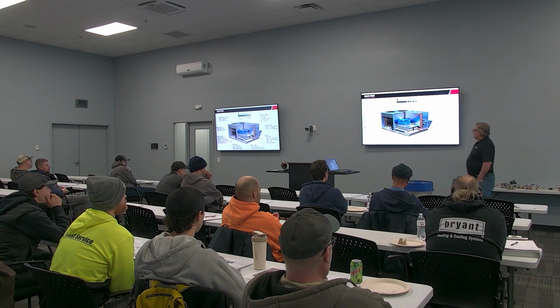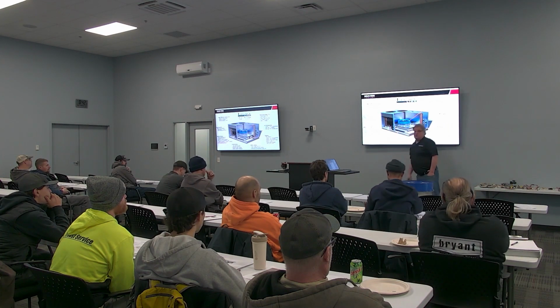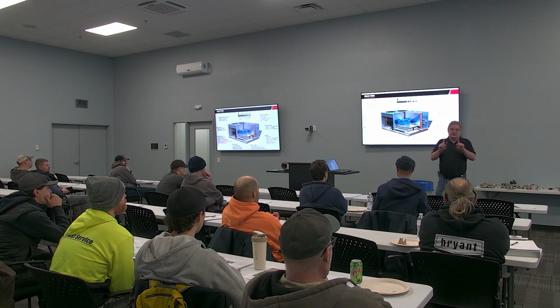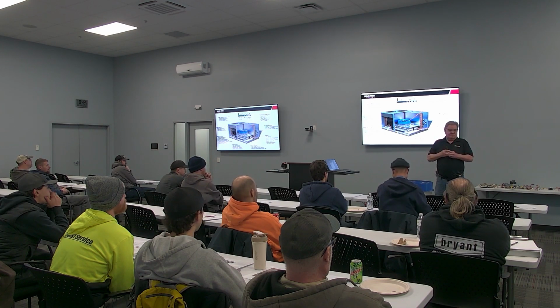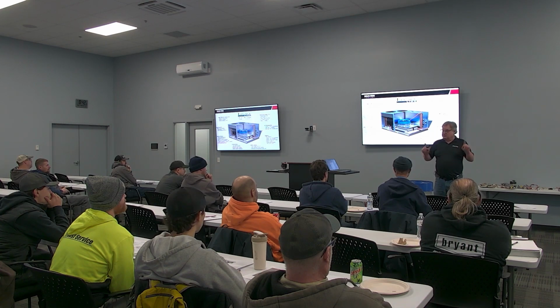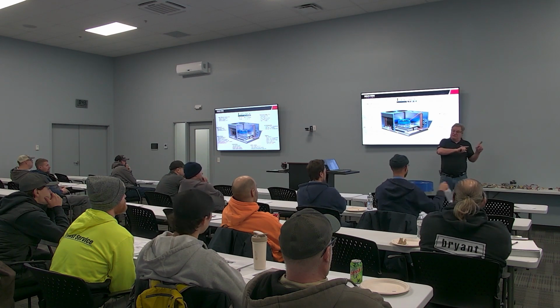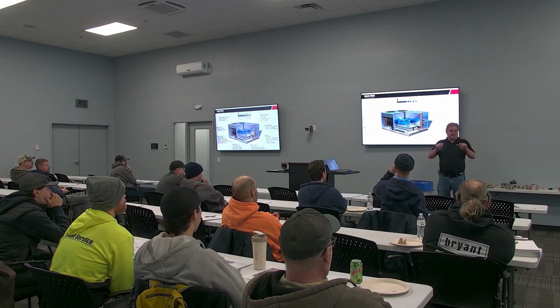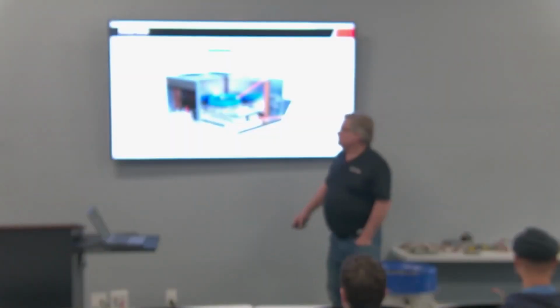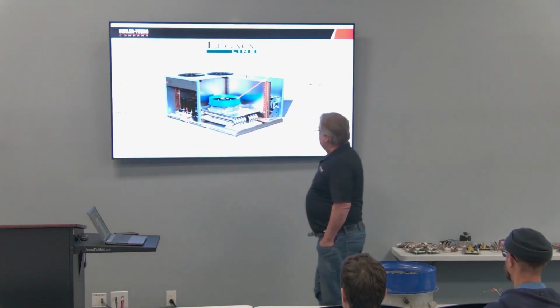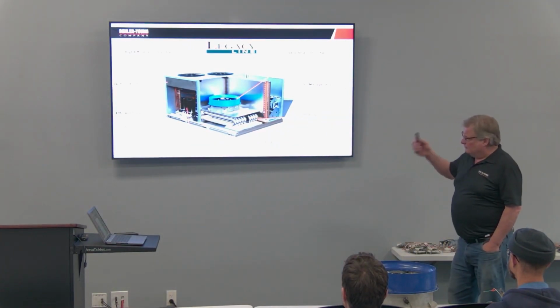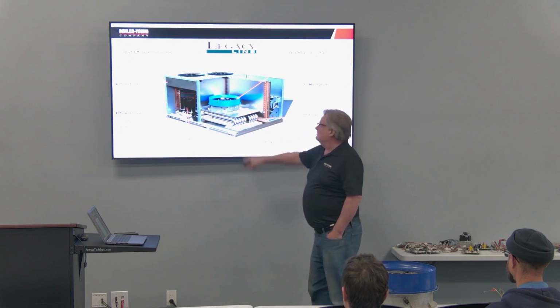The 7.5 to 12 ton, we've gone to two compressors. Now, it's a single circuit though. Does everybody know what I'm talking about? It's not 2 compressors, 2 condensers, 2 evaporators. It's 2 compressors, 1 evaporator, 1 condenser. So those compressors are piped together. They're manifolded together. Now, unlike some of the other companies who've done this, including BRYANT in the past, those are 2 separate compressors. So you can order them separately, even though they pipe together. All right. Also went to the TXV. We eliminated the flow check valve. We went to the TXV, went to the ECM motor.